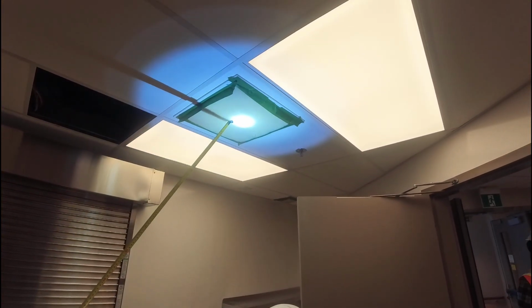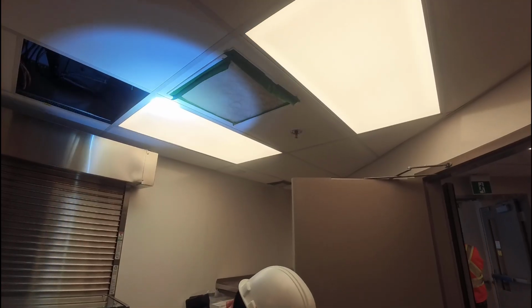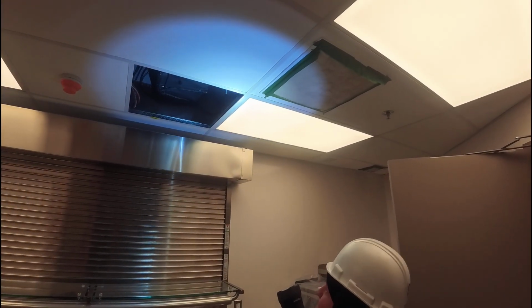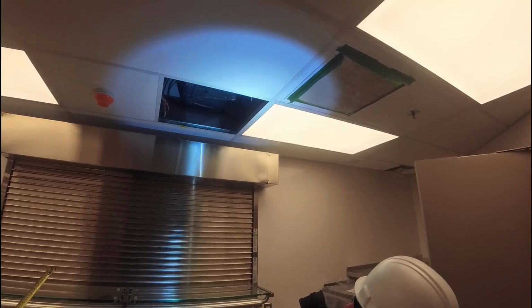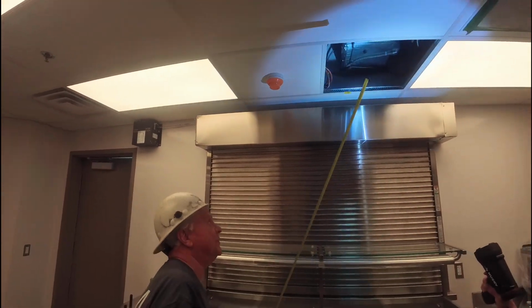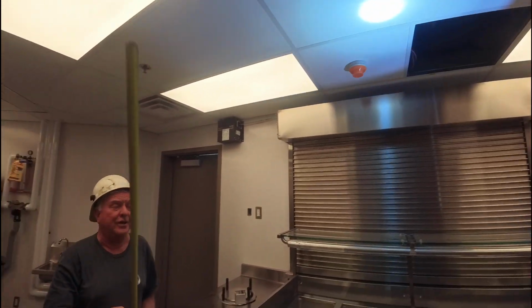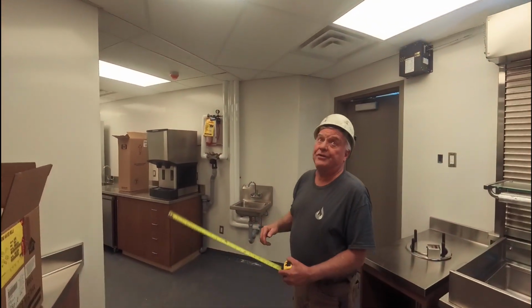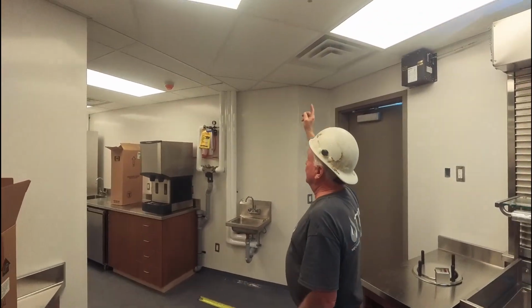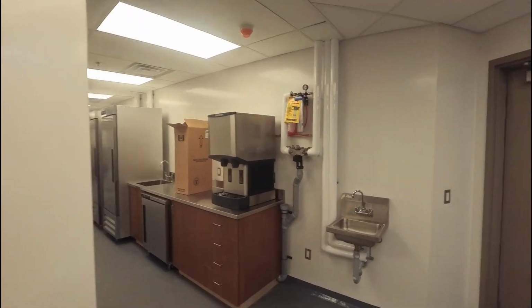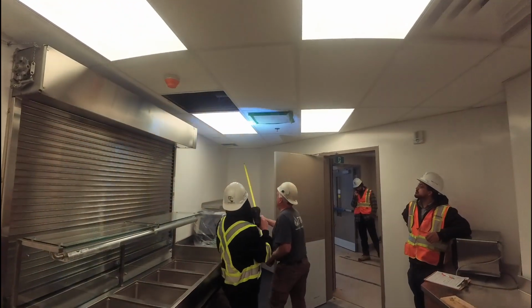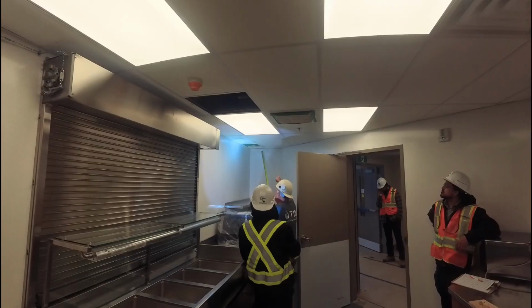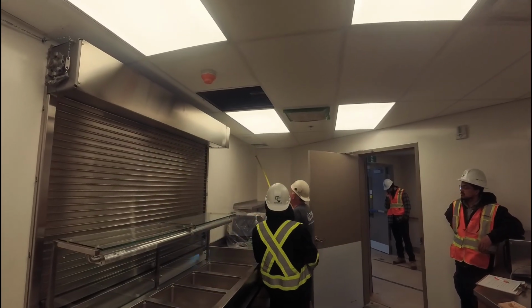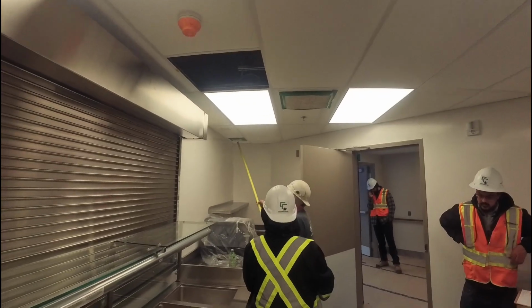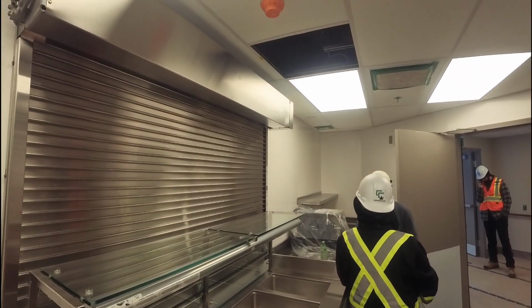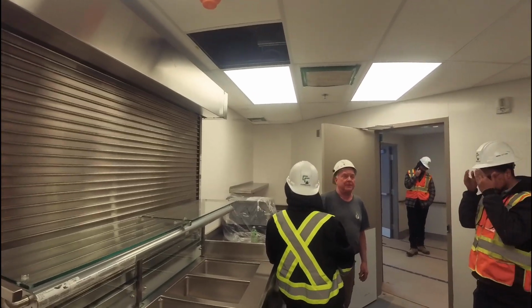And the return plenum, which is the unit above our heads, the return plenums were 18 by 18 on the servery end of it, instead of the 24 by 12s which were in the other ends. So all's good. This guy's pretty easy. He's got lots of room out here to change the filters on him. He finishes here with 1, 2, and 3 diffusers. This guy in the corner over here again has a fire damper up in the corner above. He's coming from the south east through the fire separation wall. That's an exhaust just coming off of the air handler to return air.